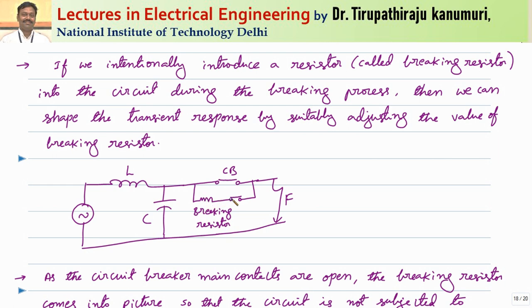Because of this bypassing resistor connected across the circuit breaker contacts, when the fault current passes, some part passes through the resistor and some part through the circuit breaker. Initially, when the circuit breaker is just opened, the arc resistance is very small — less than the breaker resistor — so the majority of current passes through the circuit breaker and some current bypasses through this breaking resistor.